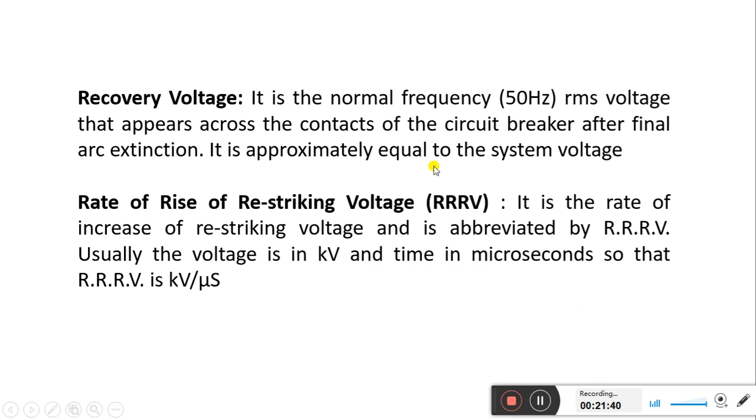The same thing has been explained here. Now one more thing is here, that is the rate of rise of restriking voltage. How can you define it? It is the rate of increase of restriking voltage and is abbreviated as RRRV. Usually the voltage is in kilovolts and time in microseconds, so RRRV is in kilovolt per microsecond.